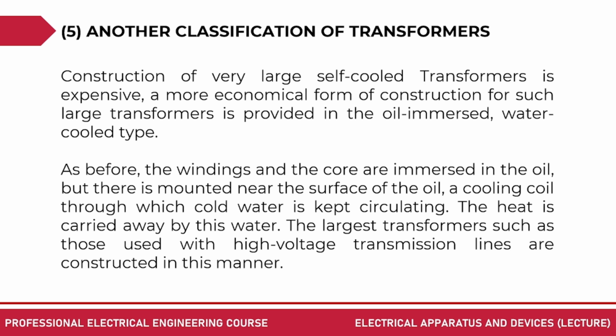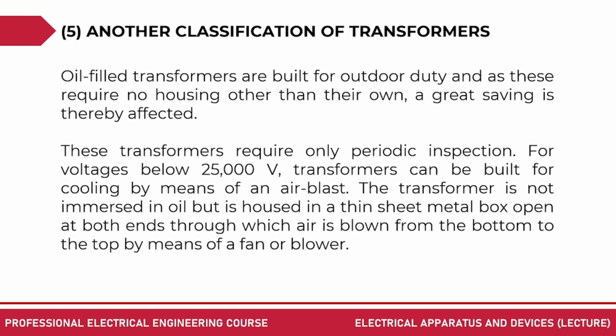A more economical form of construction for large transformers is provided in the oil-immersed water-cooled type. As before, the windings and the core are immersed in the oil, but there is mounted near the surface of the oil a cooling coil through which cold water is kept circulating. The heat is carried away by this water. The largest transformers, such as those used with high voltage transmission lines, are constructed in this manner. Oil-filled transformers are built for outdoor duty, and as these require no housing other than their own, a great saving is thereby effected. These transformers require only periodic inspection.